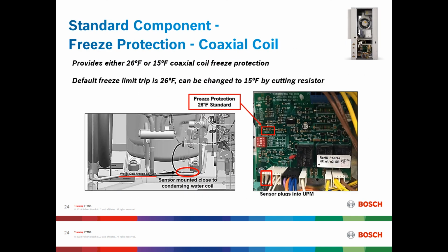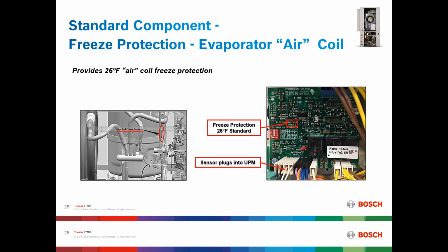These units have freeze protection on the coaxial coils, which provides either 26 degrees or 15-degree coaxial coil protection. The default freeze limit trip is set at 26 degrees, but can be changed to 15 degrees by the installer by cutting a resistor on the board. Additionally, the SMB has an evaporator air coil freeze protector. This provides 26-degree air coil freeze protection, which would occur with low refrigerant charge or airflow issues.